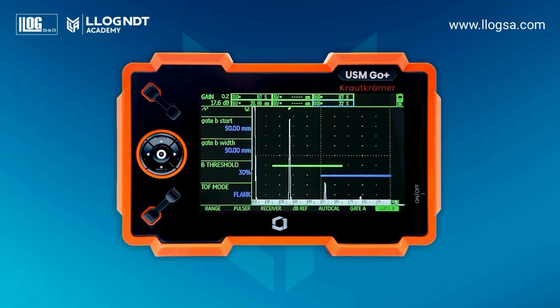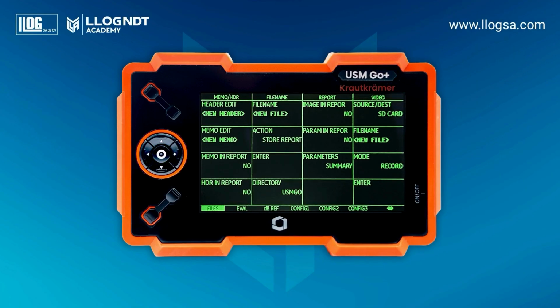In the second operating level, we find 7 additional function groups. To access this level, press and hold the center button for 2 seconds. The first group contains functions for managing calibrations, test reports, and stored videos. We can create a header or a note, and by selecting the Yes option, this information will be displayed in the report. Under the Action function, we can create a report, generate a quick report, load or delete a set of parameters or a calibration, view a report, and store a dataset.